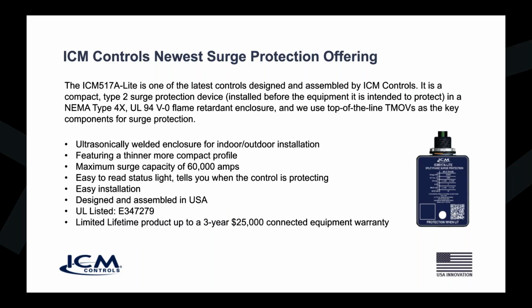But this one, the 517A and 517A Lite in this case, these are Type 2 surge protectors, so they're meant to be protected by a 15 to 60 amp breaker. So anything from a 15 up to a 60 amp breaker service being protected behind that, and then we take it downstream from there.